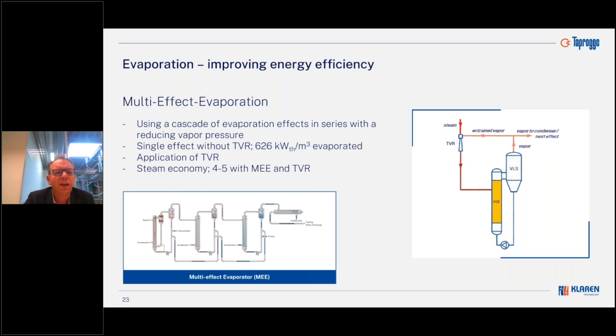And I would like to also ask specific attention for the use of a TVR, because with a TVR we can reduce the amount of vapor that at the end needs to be destroyed in the condenser. A TVR is a device which entrains vapor from one of the effects, then combines it with the motive steam, generating a secondary vapor, which can still be used as heating medium. But the main effect is that you reduce the amount of vapor that has to go to your condenser.